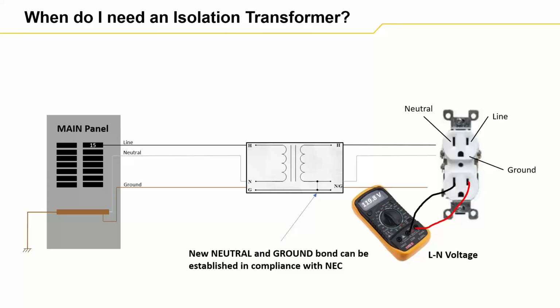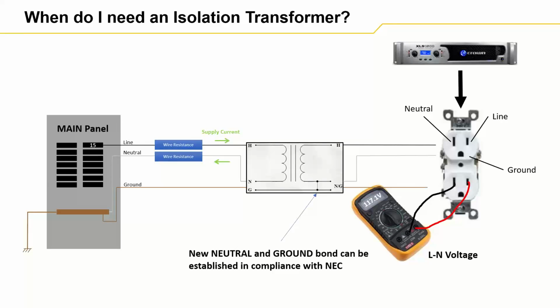When an isolation transformer is used, a new neutral to ground bond, or connection, can be safely established in accordance with the National Electric Code. This new neutral to ground bond is now much closer to the point of use, and it reduces that wire resistance, not only removing the neutral to ground voltage that's due to the current flow, but also nullifying any high frequency neutral to ground noise that might be present.